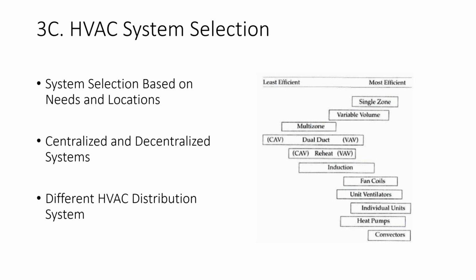There are so many principles which we can use to condition or cool the air. And there are so many ways to distribute the air, most commonly centralized and decentralized systems. And even in the centralized systems, the distribution could be single zone, variable volume, multi-zone, duct, dual duct, reheat, induction, fan coils, unit ventilators, individual units, heat pumps, and convectors. That's just the centralized system distribution.